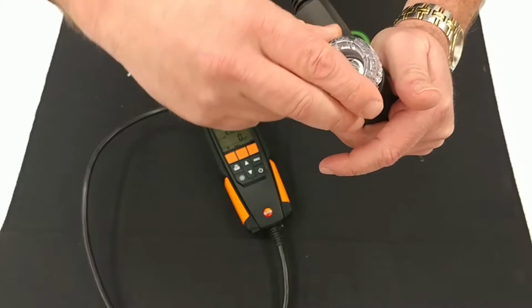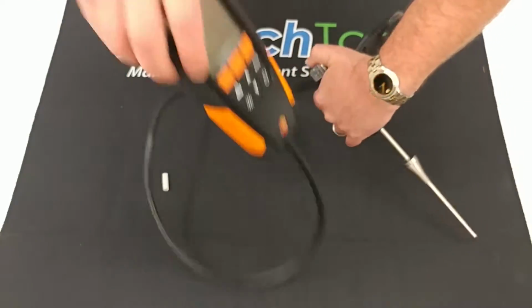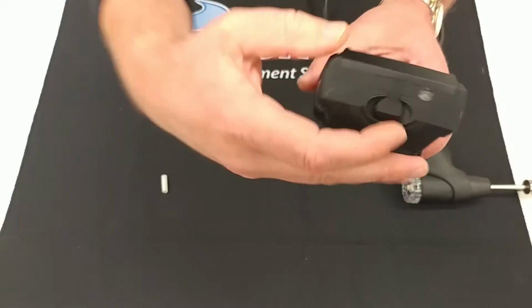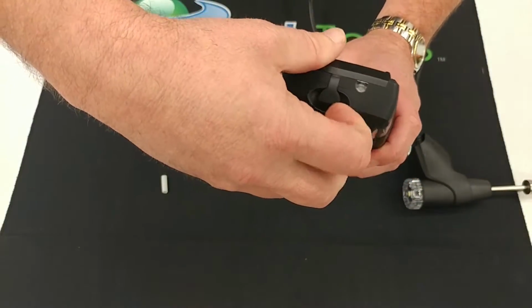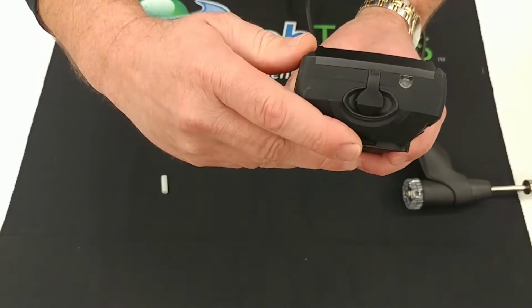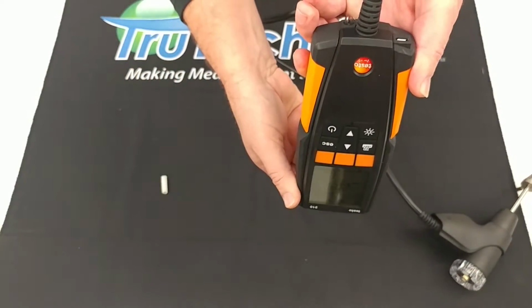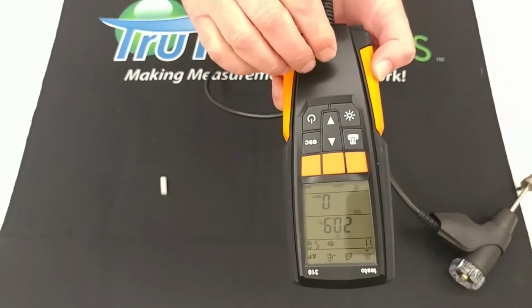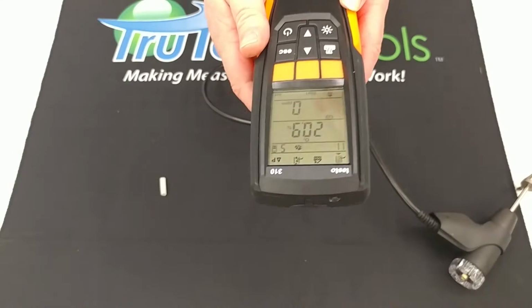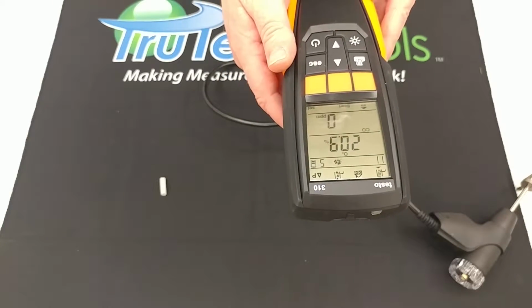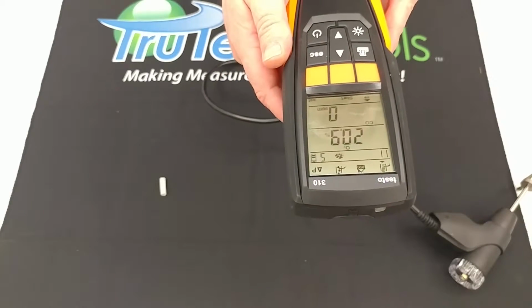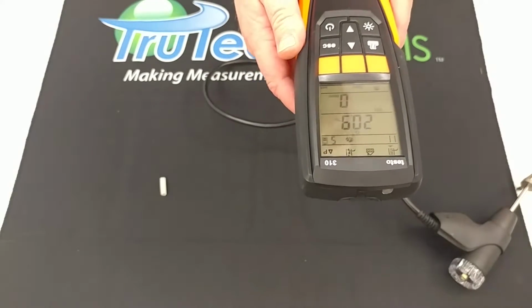The last function that I want to talk about on this particular piece is the water trap. It's a very accessible, very easy to get to water trap on the unit. As for the condensation on it, basically tip it upside down to empty it. Important feature, guys: if you're working in cold environments and you're leaving your tools in the van and they got water in them, it's going to freeze overnight. So make sure you empty your water traps.